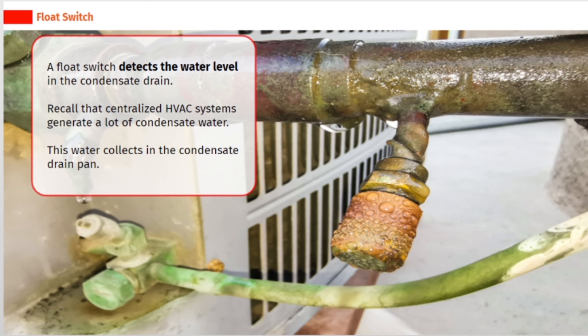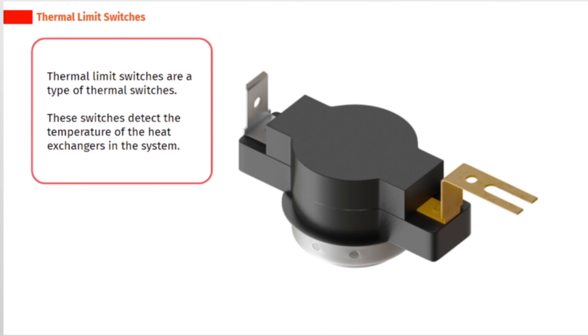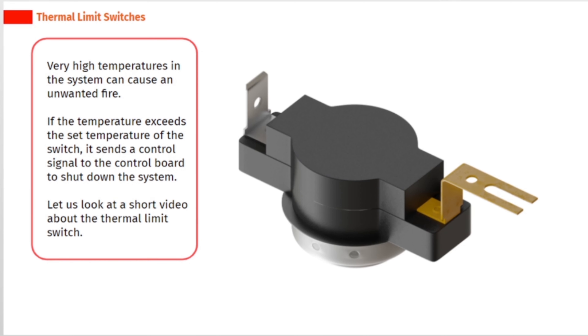A float switch detects the water level in the condensate drain. Centralized HVAC systems generate a lot of condensate water, which collects in the condensate drain pan. Safety controls specific to the heating part of the centralized HVAC system include the flame sensor, flame roll out switch, thermal limit switch, and exhaust draft pressure switch. Thermal limit switches detect the temperature of the heat exchangers. Very high temperatures can cause an unwanted fire, so if the temperature exceeds the set value, the switch sends a control signal to the control board to shut down the system.